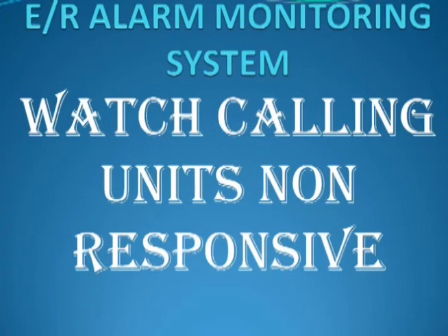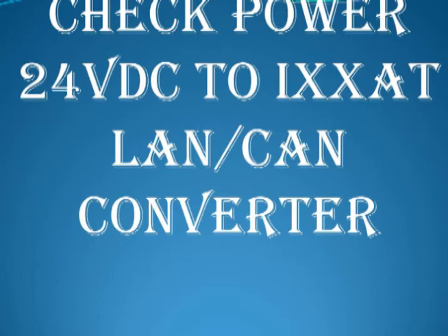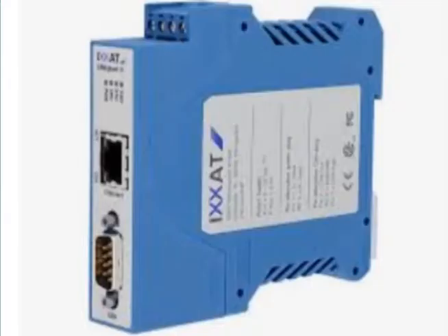In case watch calling units are not communicating with ROS, check power 24 volt DC to the IXXAT LAN-CAN converter. IXXAT is the blue converter inside the console.